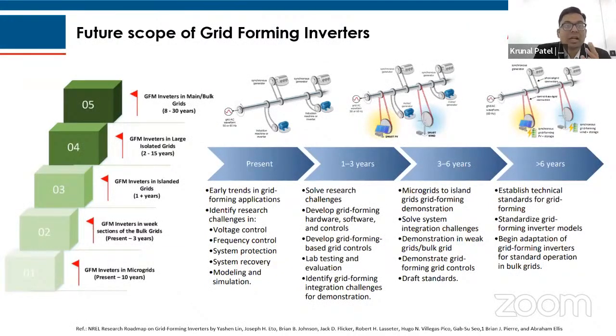And lastly, I wanted to explain the future scope of grid forming inverters. This is one of my favorite slides. Currently we are at this stage of grid forming inverters in a microgrid. Later we have to move further, to grid forming inverters in weak sections, where it becomes like a bulk grid scenario. Then it should be in a completely islanded mode. That islanded mode becomes large isolated grids, and at the last, fifth stage, grid forming inverters become the main or bulk grid scenario.